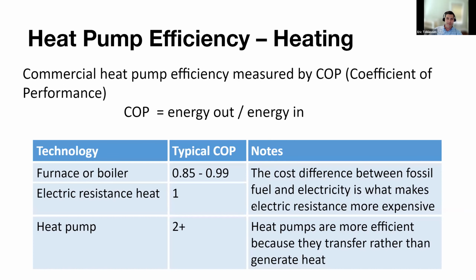And then looking at heat pump efficiency for heating, it's measured by COP, which is called the coefficient of performance. And the COP is basically energy out divided by energy in. So any COP below 1, you're actually getting less energy than you're putting into the system. If you look at a furnace or boiler, those are about 85% or 99%, or have a COP of about 0.85 or 0.99, which means you're actually losing energy with these systems. Electric resistance heat has a COP of 1. The energy you're putting into that electric coil, you're getting out as heat. And then heat pumps can actually get up to higher COPs, so the average is around 2. So you're actually getting more energy out of a heat pump system than the energy you're putting into it, even at low temperatures.